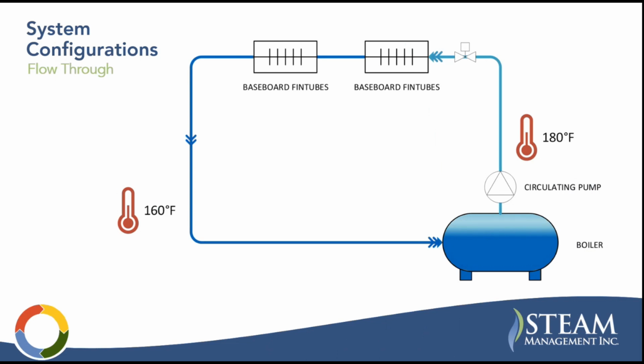This is what's called a flow through configuration. This is one of the simpler configurations. You have your boiler, and your pumps circulating water out of it. Basically all of your users are in series, so you're flowing through all of your users. There's no parallel flow path. It just goes through all the users and comes back.